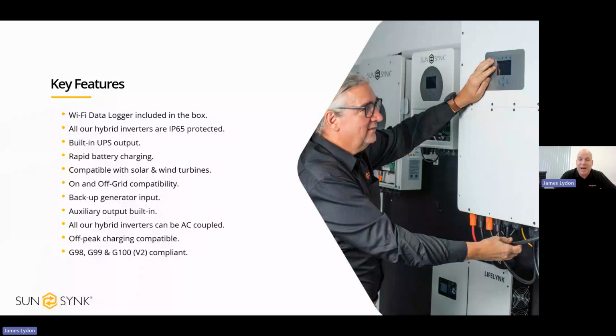The limitation on that output is the rated value of the inverter. So if you've got a 5 kilowatt hybrid inverter, depending on what the battery SOC is and what the PV is generating, the maximum you can take out of that output is 5 kilowatt.